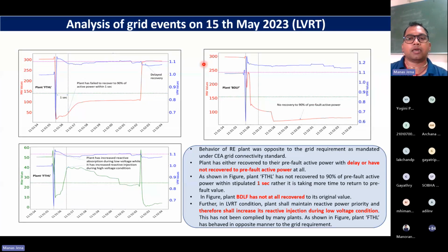You see, again red color. Megawatt was good. Fault happened, event happened. Megawatt goes down, but it could never recover. No recovery to 90% of pre-fault active power. It could never recover. Third, this one. This is the MVAR, reactive power. Okay, so green color was the reactive power. You can see that when the event happened, it momentarily goes down, and then this particular plant FTHL has increased the reactive power absorption during the low voltage, while it has increased the reactive power injection during the high voltage condition.